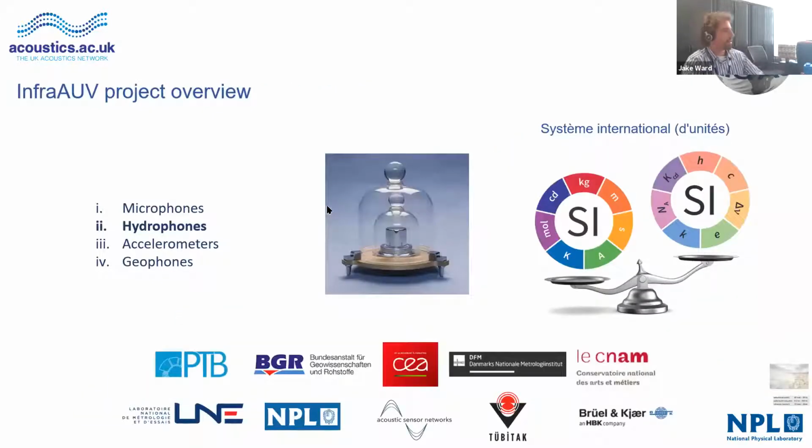So the project then, this project in infrasound, Infra AUV, has partners across Europe here, and aims to come up with both primary and secondary calibration techniques. What I mean by that is a primary calibration technique relates the acoustic Pascal, so force per area, to the International System of Units, so the SI.